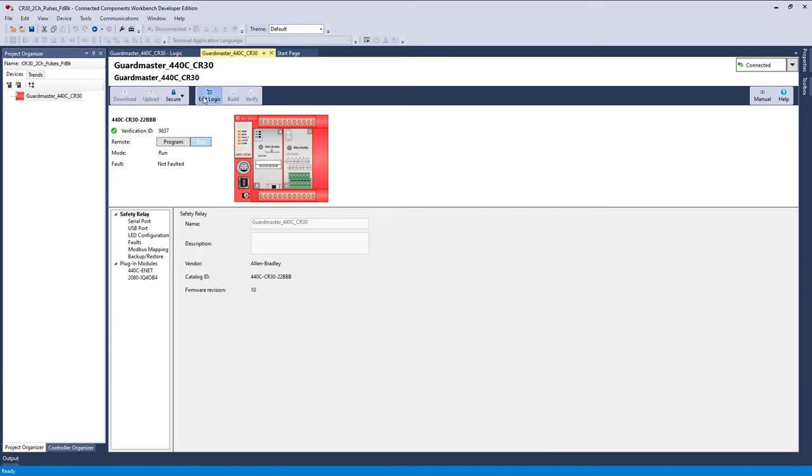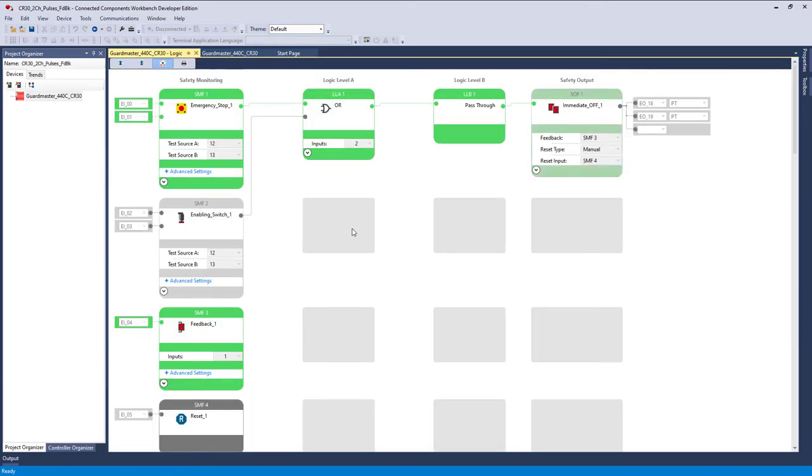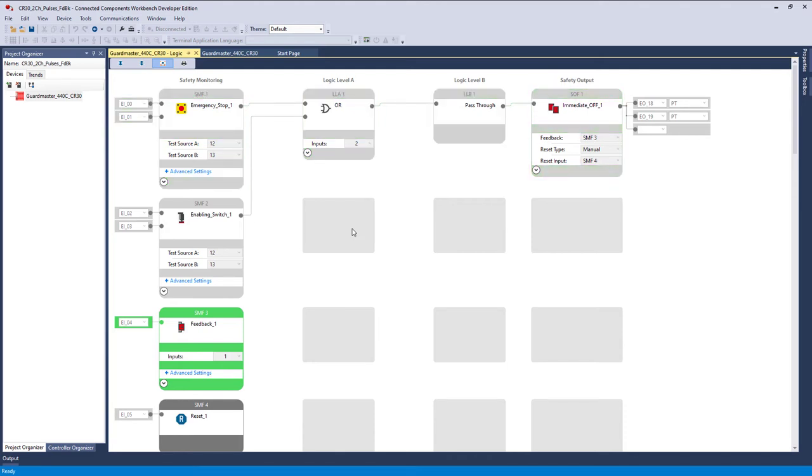Going to edit logic. And there we are. So our feedback is good. Everything is good. Let's do an e-stop. Now nothing turned red because remember, pushing the e-stop is not a faulted condition. The fact that everything is either grayed out or green means that everything is normal.